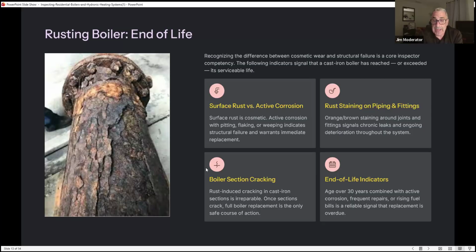I will just let my client know where it is on the age of the life. I'll check the service tag to see the last time it's been serviced, and sort of give my client an idea where we are on the life cycle with the unit. I do try to run all the zones all the time. Okay. And then I'll turn on all the thermostats, but then what I'll do is I'll physically touch the zone pipes coming out, the supply pipes coming out, to see if they're warm or hot, and see if the circulators are working. So that's what we do there.